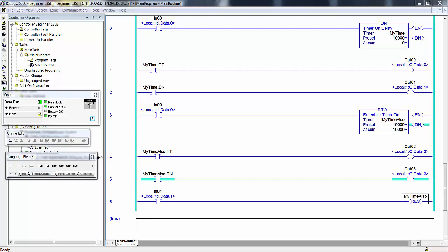Now we have a reset for the RTO, rung 6. I told you to add this rung of logic to your routine. It doesn't have to be the last rung. Location in the logic at the most could affect the reset by 1 scan time difference, 20 microseconds or so. In some logic, this could render other logic non-functional, but not in this instance.